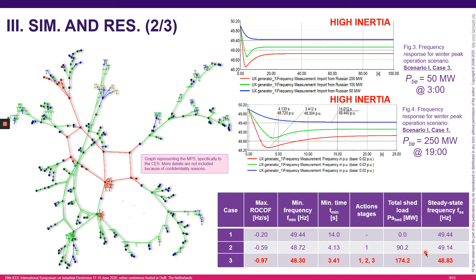However, the most important scenario is the low inertia scenario. The low inertia scenario, as I said, is the summer, because people go to the countryside, the demand is reduced, many big generators are disconnected, especially CHP, and as a consequence, the inertia is quite reduced, okay?